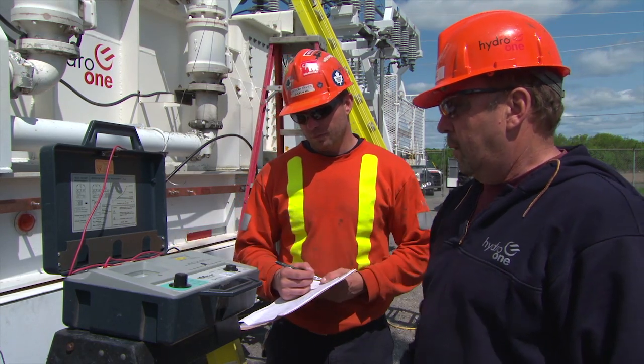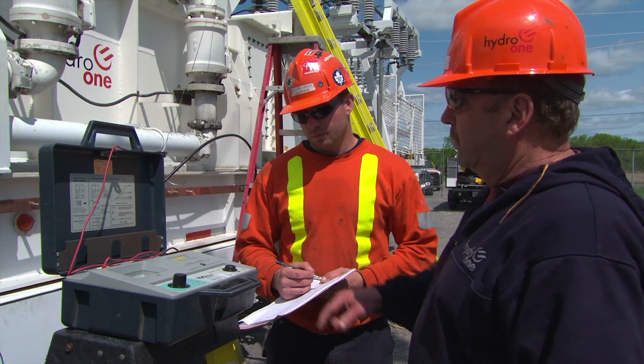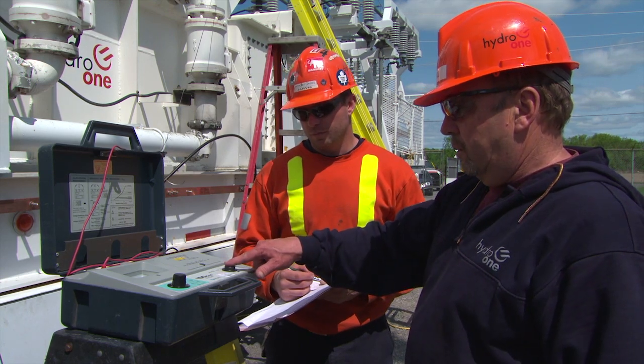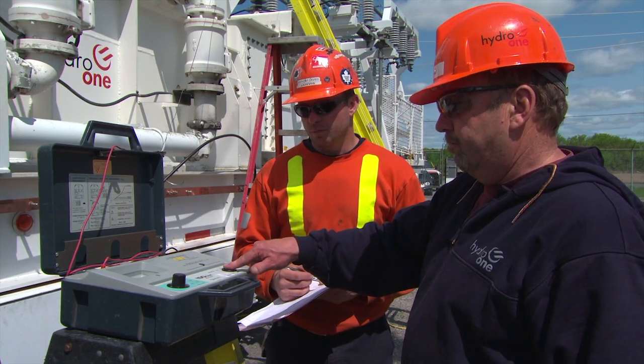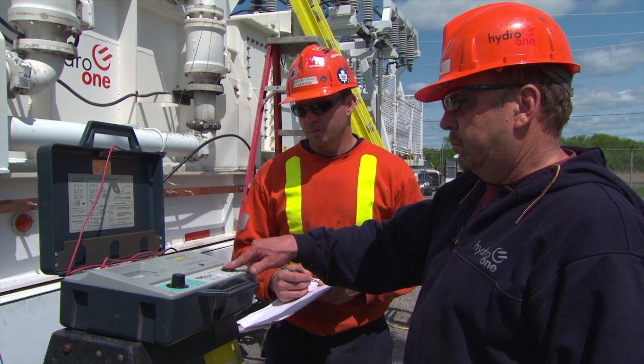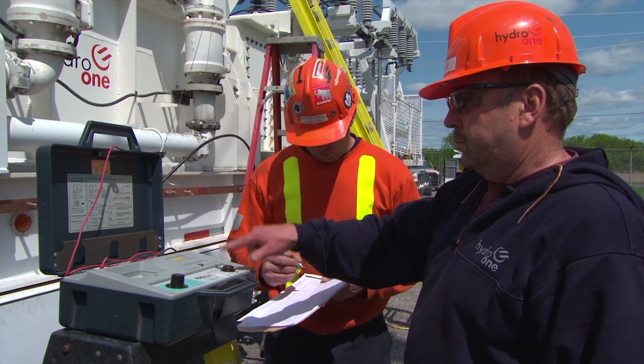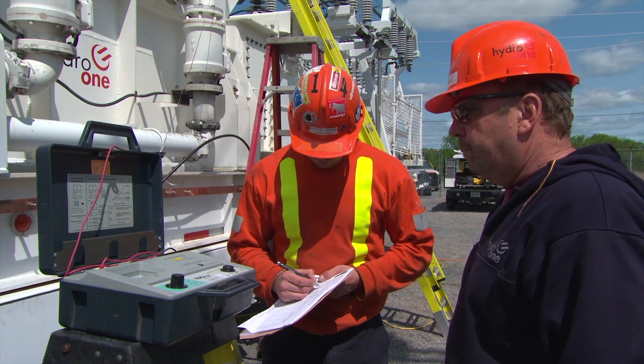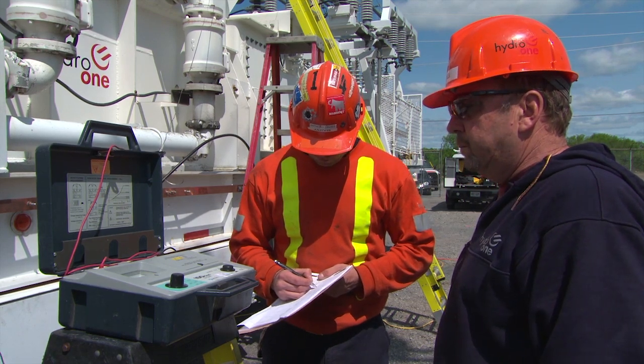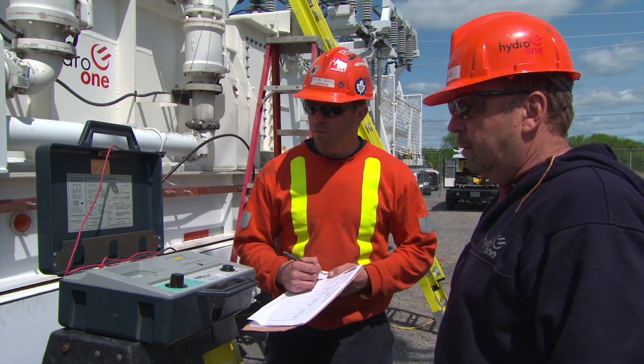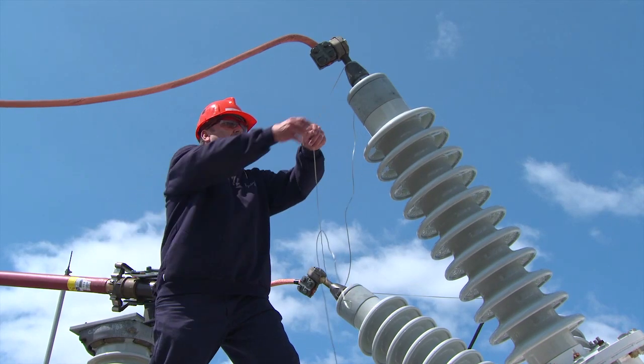Then disconnect the high-voltage and low-voltage windings from ground and short those leads together. Place the megger lead on the windings. Ensure all employees are clear of the area and perform the high-voltage and low-voltage windings to ground test. Record results and ground the high-voltage and low-voltage bushings.